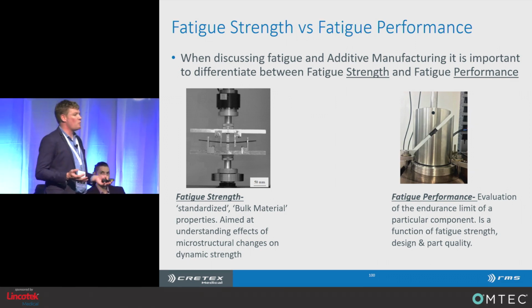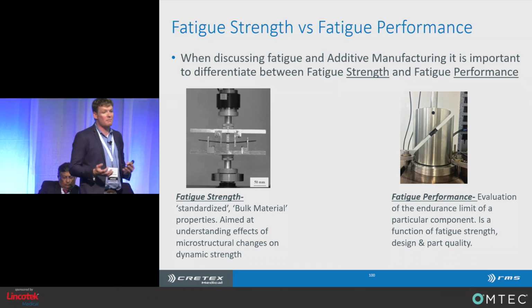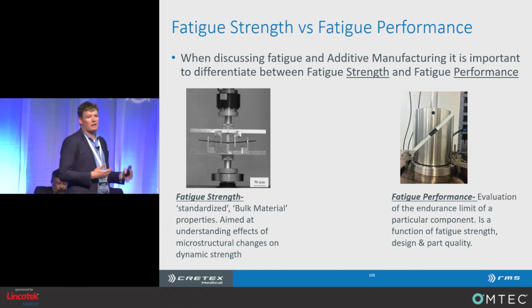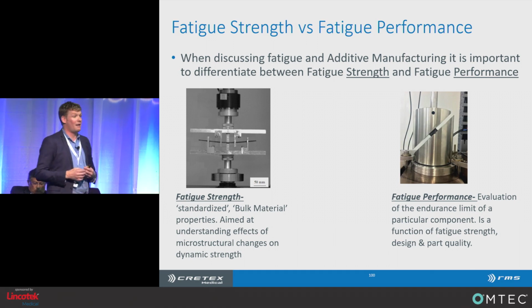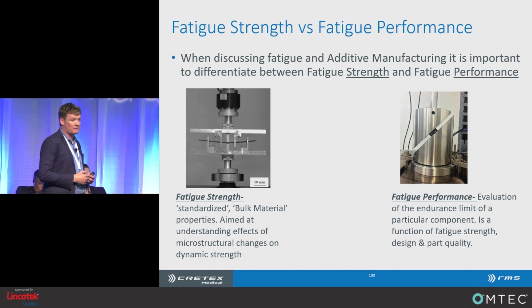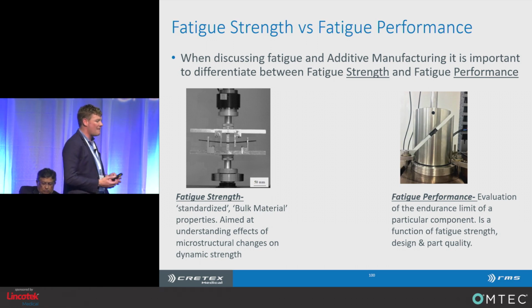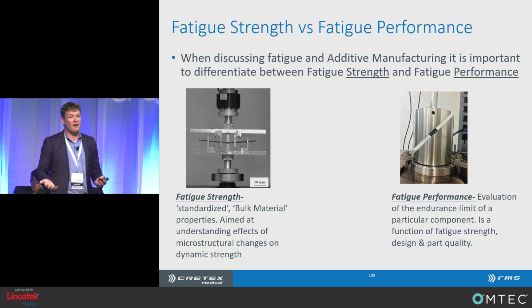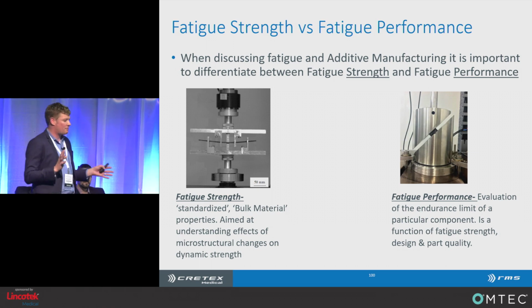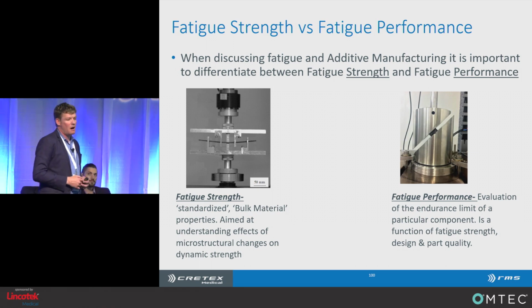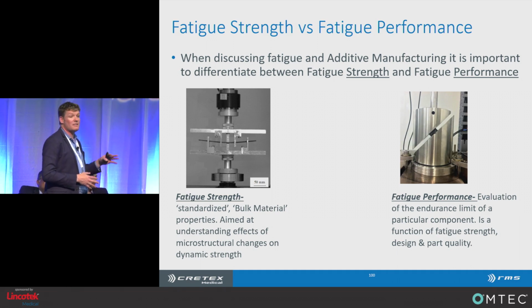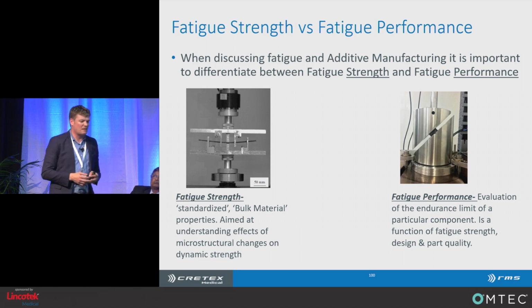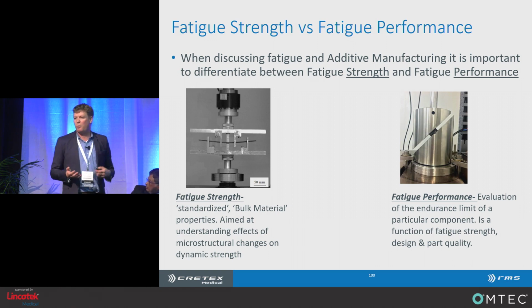Typically evaluated using standards that try to eliminate a lot of other variability that could influence the results. Those are typically done on highly polished samples so that we can really focus on the bulk material properties, right? And then there's fatigue performance, which is how much fatigue your device can actually withstand in its operating conditions. The reason I want to differentiate between the two is because there are things we can do with our additive processes to influence the fatigue strength of the material, but it's much harder to influence the fatigue performance of an additive device through processing, and I want to go through what creates that situation.